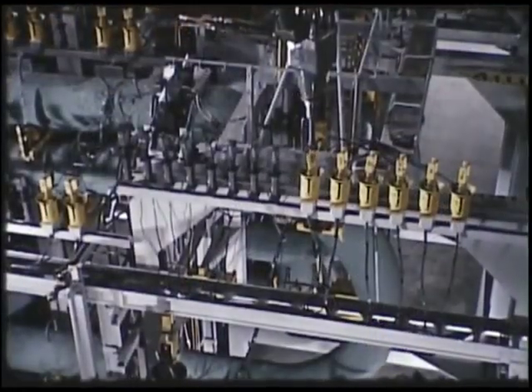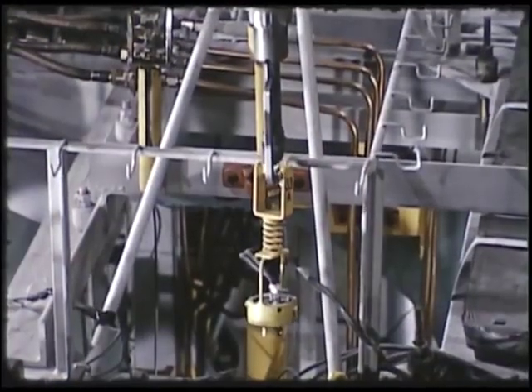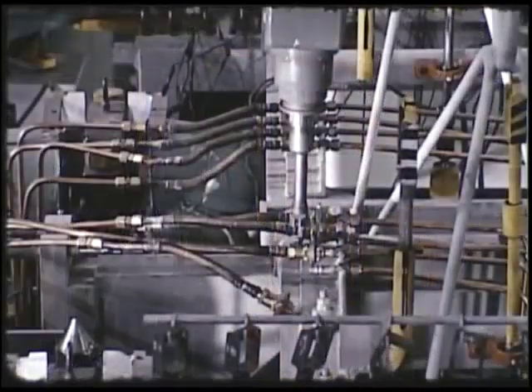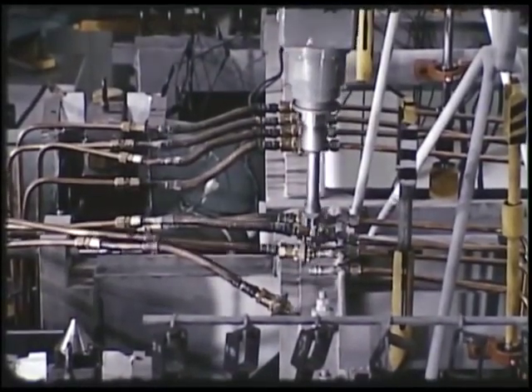The first step in replacing a heat exchanger is the disengagement of 23 thermocouple and heater leads. These connectors are hung nearby for easy pickup and reconnection. 8 forced air cooling lines servicing the 4 heat exchanger flanges are also disconnected.